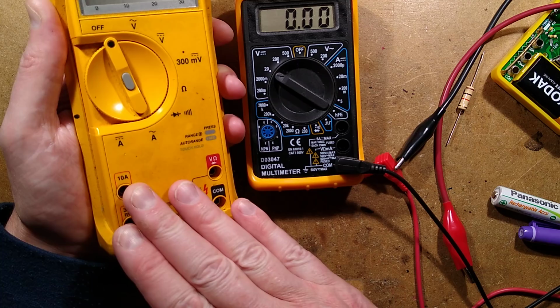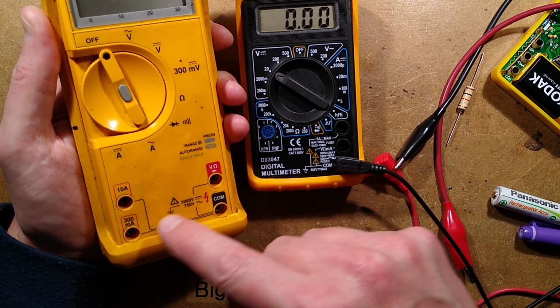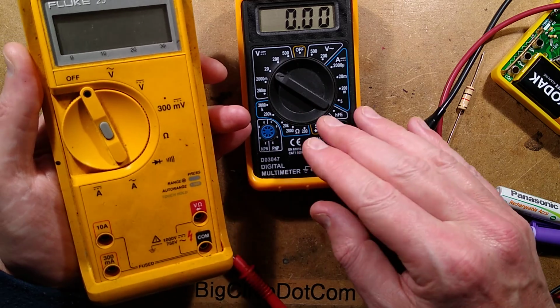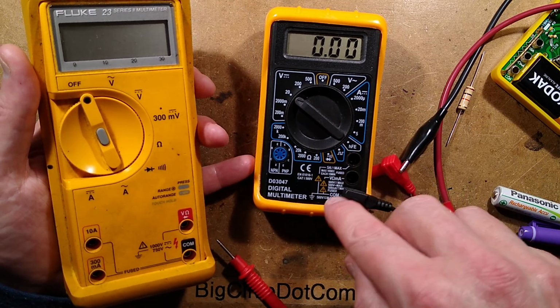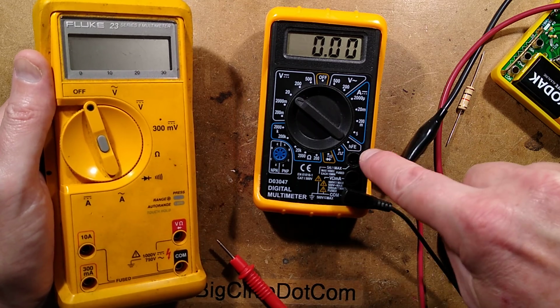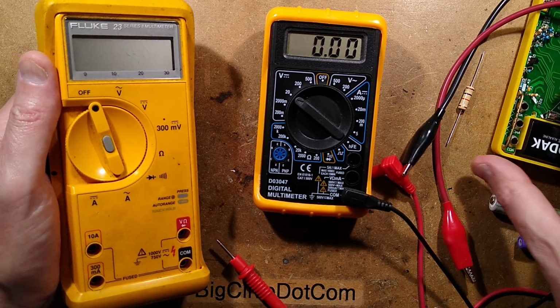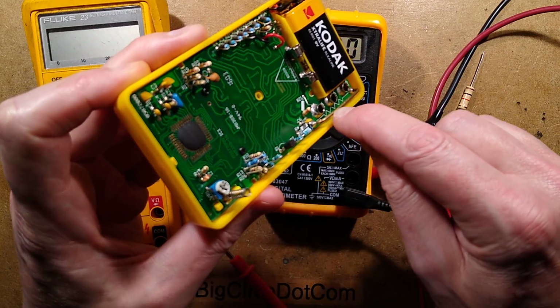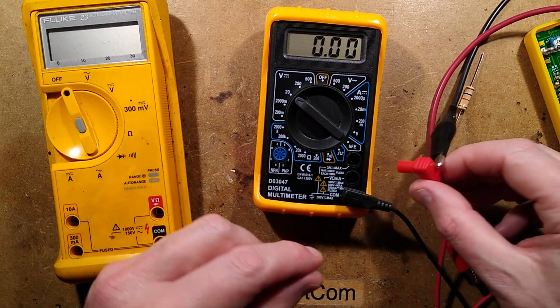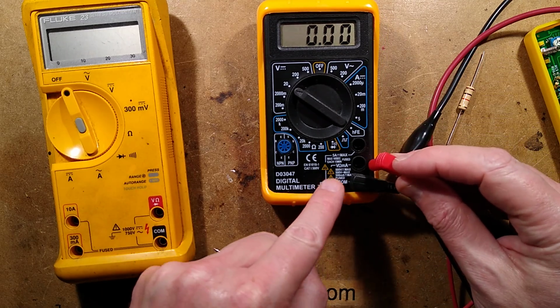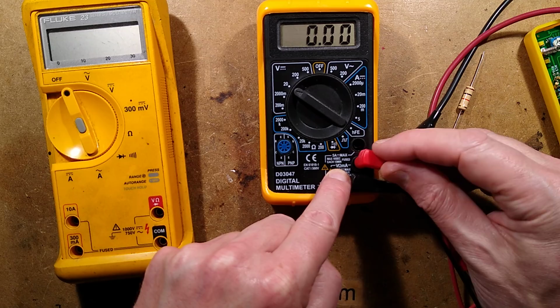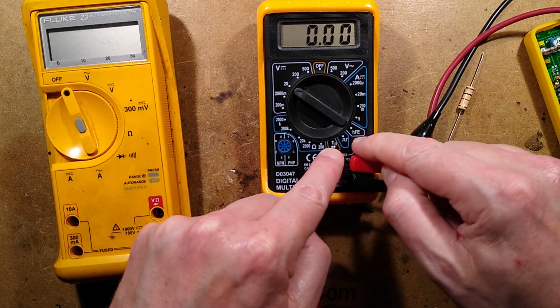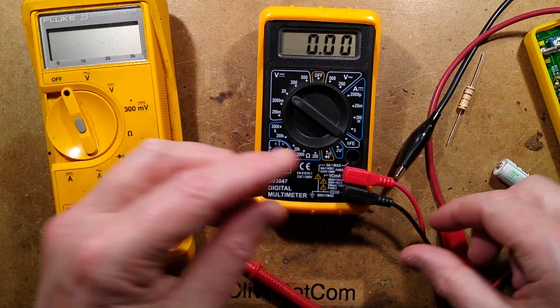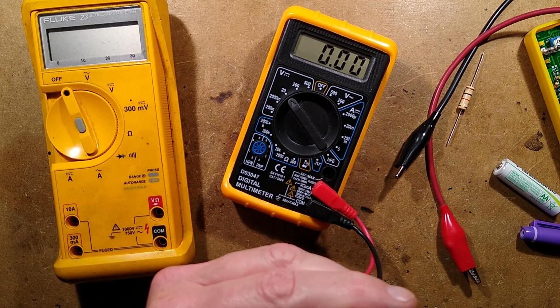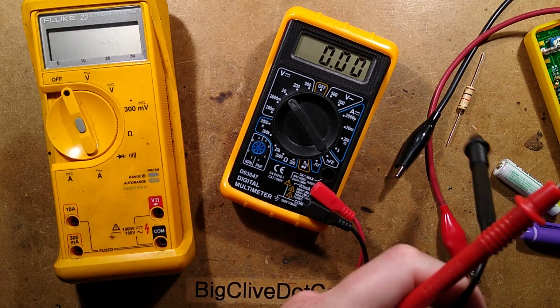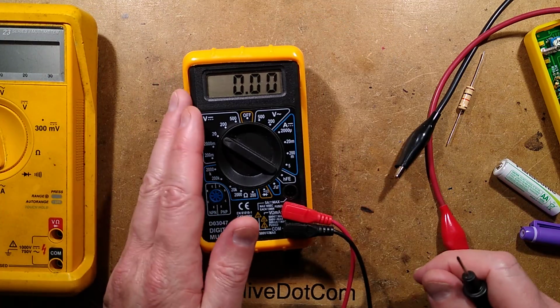The reason they normally keep the current ranges separate is because when you put them into the current ranges, by the way it measures the current, it puts a very low value resistor or a dead short across it. If I was to probe across the 5 amp connection in this, or 10 amp, depending on the type of meter, you'd see the shunt. It's really important to make sure the lead's in the right place. In almost all instances, you will have the black in the common and the red in the volt ohm milliamp. If you put it into the 5 amp one, or the 10 amp one, you're not going to get readings, but you're going to short circuit everything you put this across. It's worth knowing that. What's the next range?